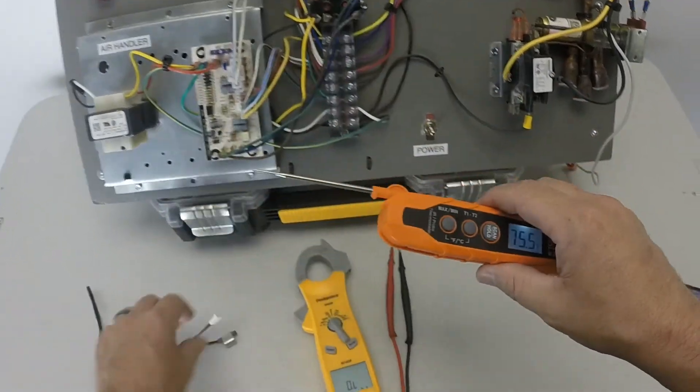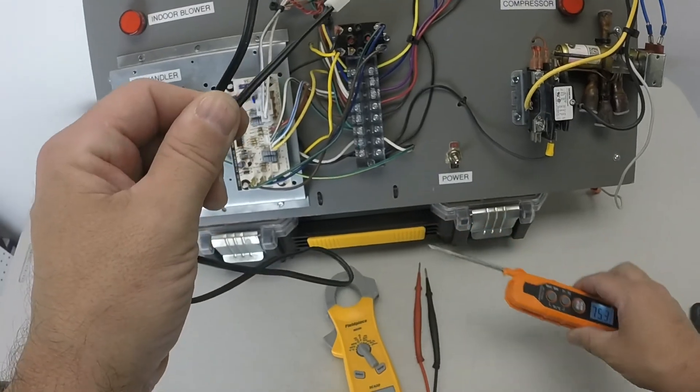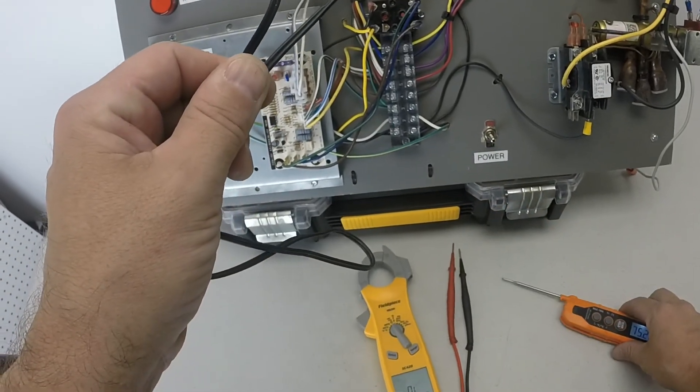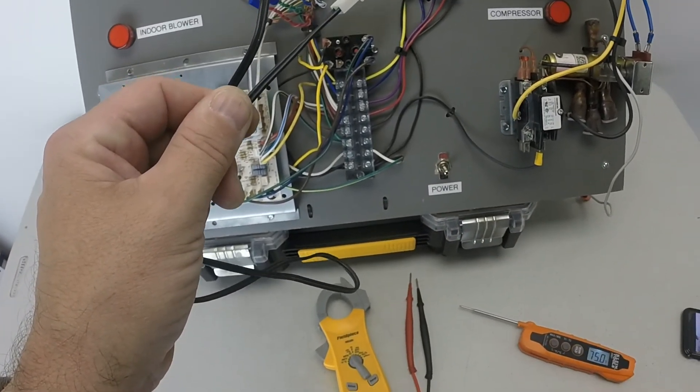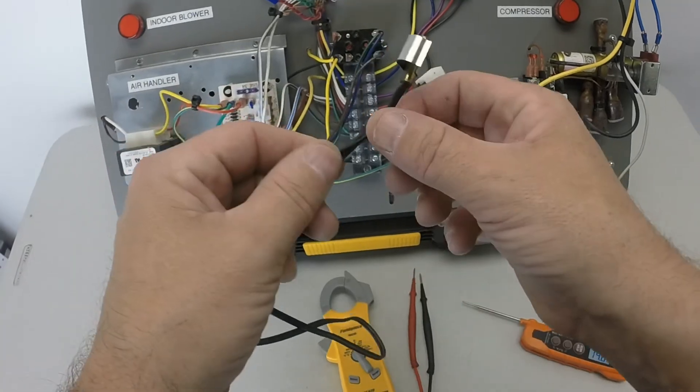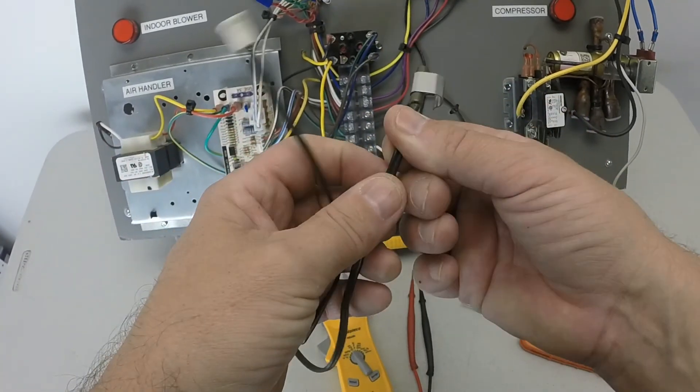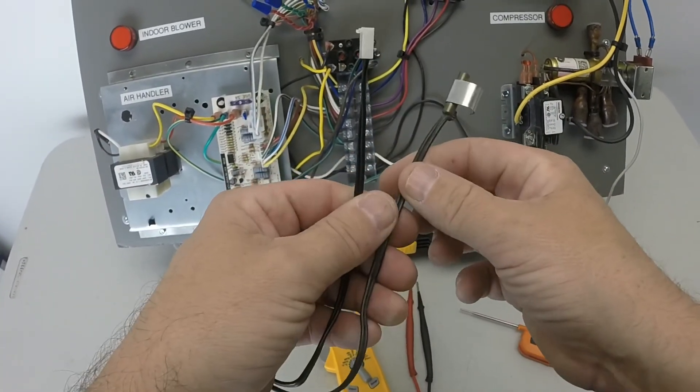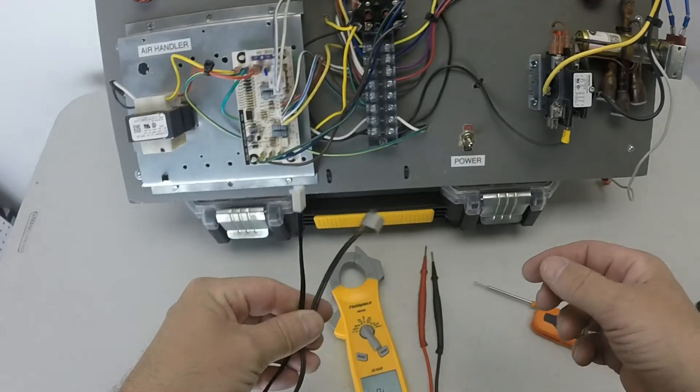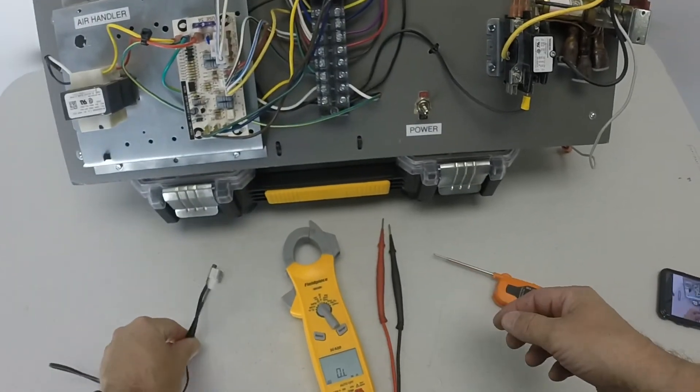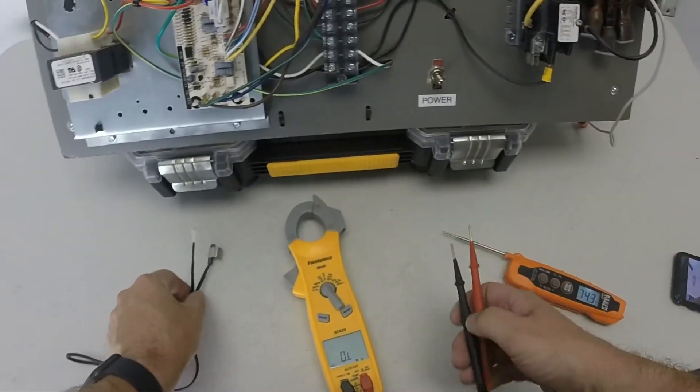If this thing is still on the coil right and the coil is frozen, you're not going to be able to check that. Best thing to do is just go ahead and take it off, unplug it from the board. Now let's check it.